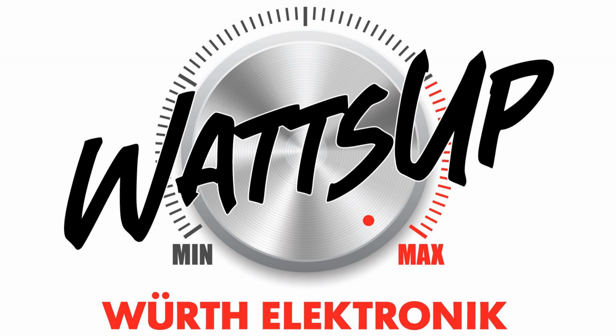So this is how it looks graphically. Up to the limit ambient temperature, which is here on the x-axis, we can apply 100% of the rated current, and then the current has to be reduced in a square root manner. But at the maximum operating temperature, which is reached here, for example, 125 degrees Celsius, the current has to be reduced theoretically to zero. That means no more current allowed.